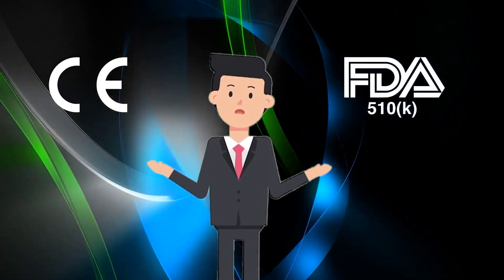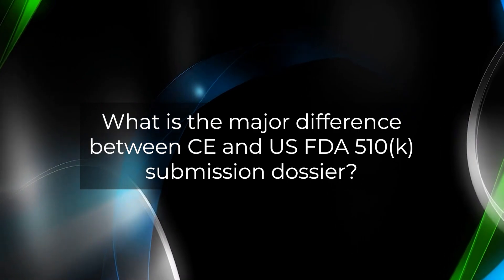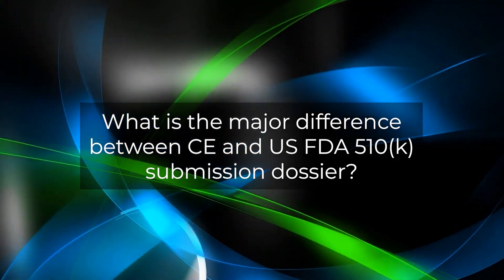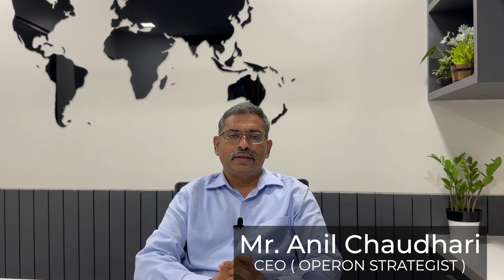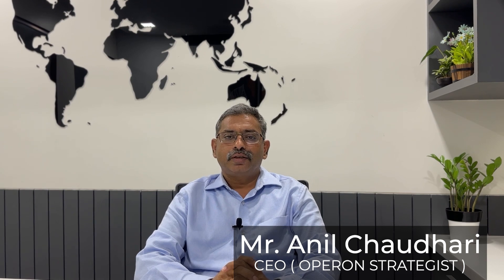Hello Mr. Anil, let's get started. The first question is: what is the major difference between CE mark and US FDA 510k submissions? As far as CE marking goes, the major basis of submission is a clinical evaluation, proving that the product is safe and effective through risk assessment procedures. However, when it comes to 510k, the basic assumption is how equivalent the device is to a predicate device already being sold in the US. So the entire basis for both submissions is very different.